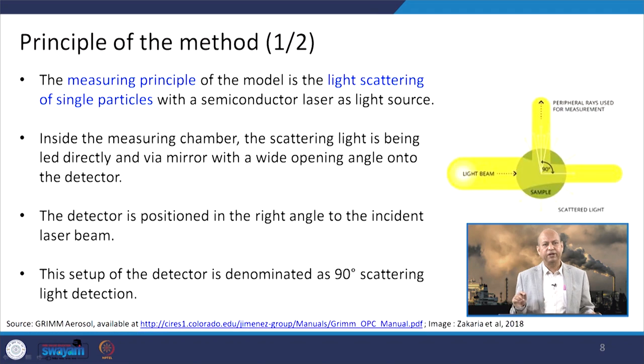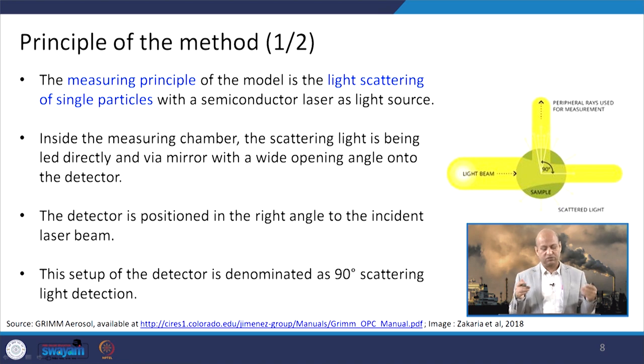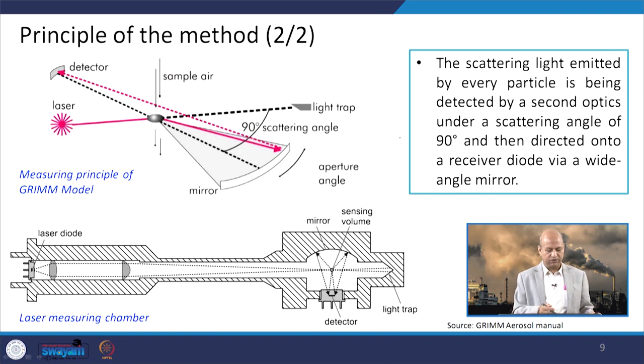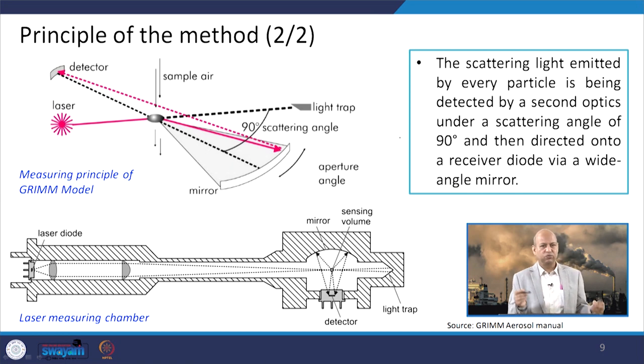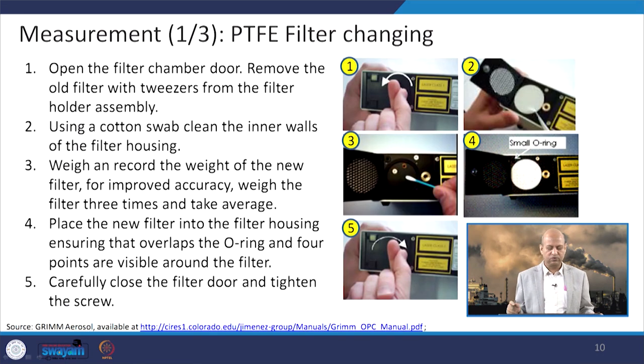The sample inlet at port 4 is where air inflows. Analog input is port 5, port 6 connects to the main adapter, and port 7 is the interface port for connecting to a desktop computer. The back panel has space for the filter paper and outlets for cables. The basic principle used by the spectrometer is light scattering by a single particle. This is why the instrument gives not only mass concentration but also count — the number of particles. The laser passes at 90 degrees; when it strikes a particle, it scatters the light, which is reflected through a mirror and detected by the detector, recording the number of particles and mass concentration.